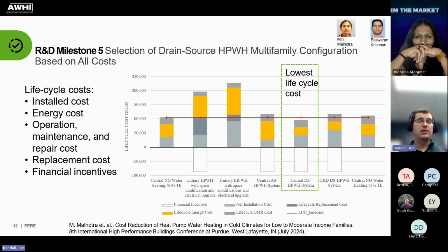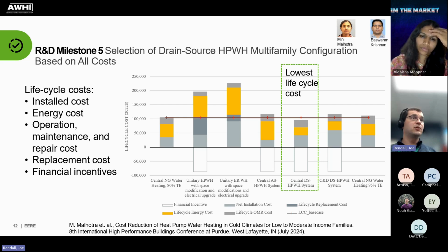When you electrify a unitary heat pump water heater through the IRA, there are significant incentives per unit. We applied that same incentive to our centralized drain source systems and came out with a slightly lower life cycle cost than centralized natural gas at 80% thermal efficiency, which is pretty good out in the field. That gave us confidence to move forward with the rest of the project and the experimental work, since we ended up with the lowest life cycle energy costs.